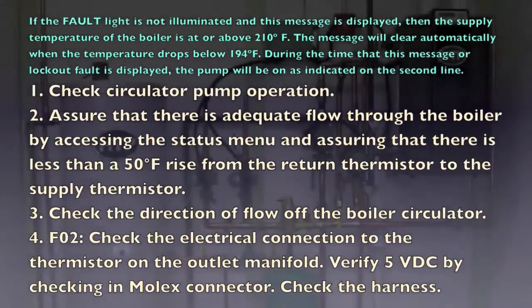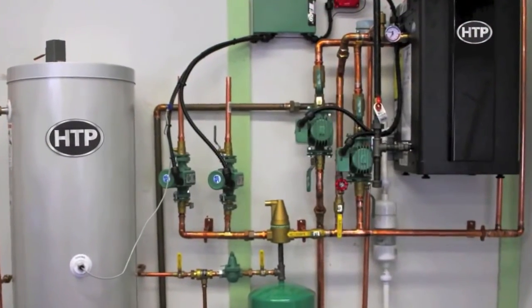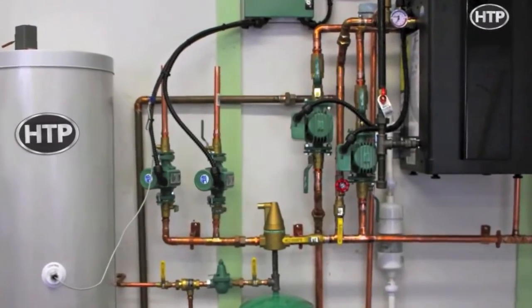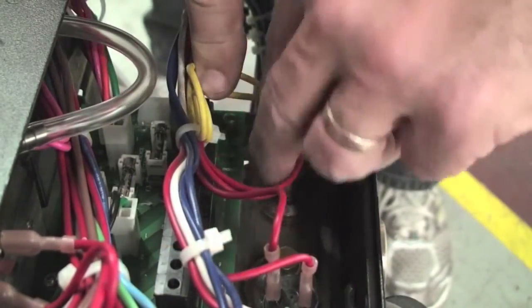If you have checked the circulator function and the boiler does not appear to be hot, then check the supply sensor fault F02. If you continue to have an issue, please call the factory for further assistance.